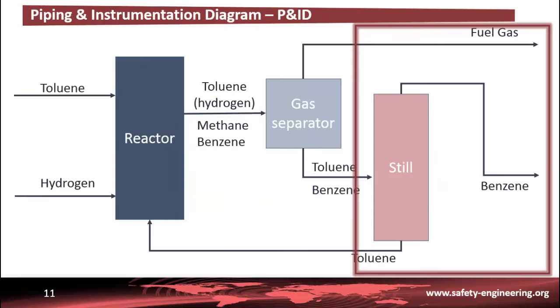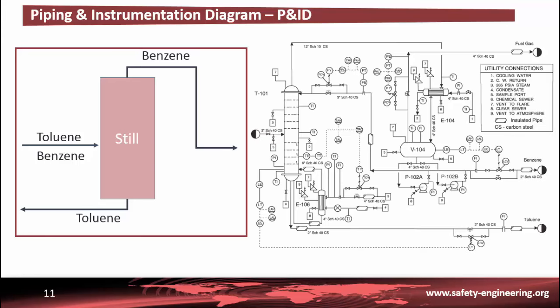In this slide, you can see the P&ID for the distillation part of the process in order to separate the benzene product from the unreacted toluene. This P&ID diagram shows the layout of the process equipment, piping, pumps, instruments, valves and other fittings. It includes all process equipment. These pieces of equipment have to be drawn roughly in proportion. All pipes are sometimes identified by a line number. The pipe size and type of construction material should be shown. The materials may be included as part of the line identification number. All valves, control and block valves may be shown by the symbol used for the valve or included in the code used for the valve number. Pumps are identified by a suitable code number. The control loops and instruments are shown with an identification number.